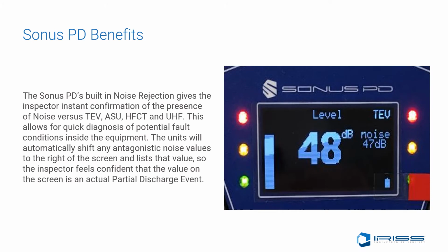The Sonus PD's built-in noise rejection gives the inspector instant confirmation of the presence of noise versus TEV, ultrasound, HFCT, and UHF. This allows for quick diagnosis of a potential fault condition inside the equipment. The unit will automatically shift any antagonistic noise values to the right of the screen and list the value, so the inspector feels confident the value on the screen is an actual partial discharge event versus antagonistic noise.